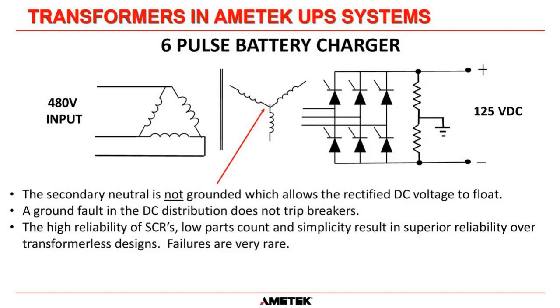I really like this kind of battery charger because it's simple. SCRs are the rectifier. They are incredibly reliable and rarely ever fail. This battery charger, therefore, is very simple. The controls are simple, and they just run and run and run.